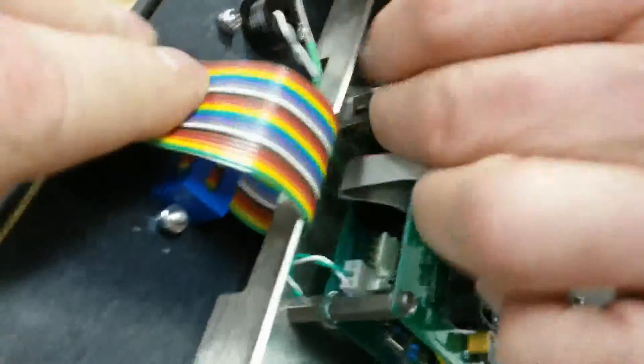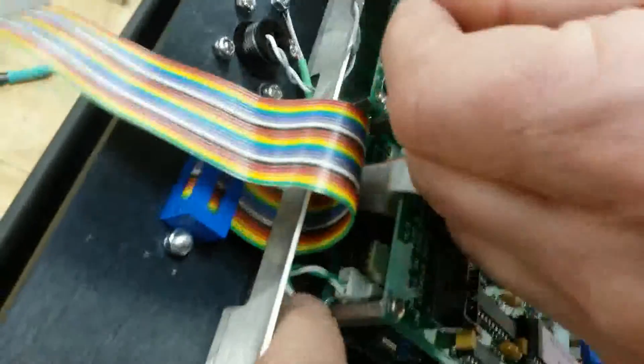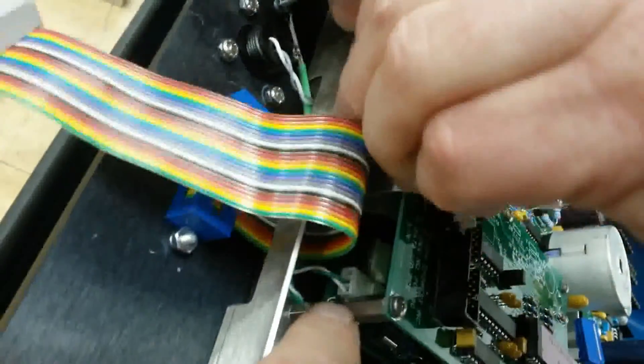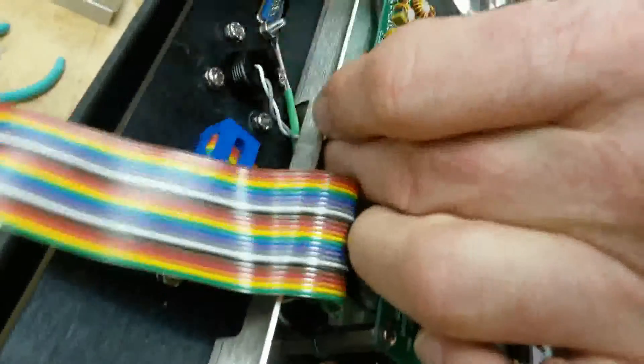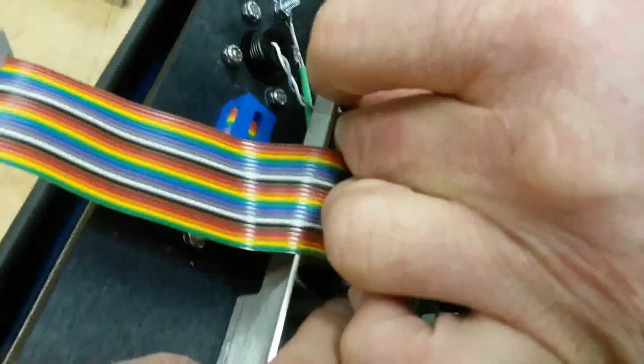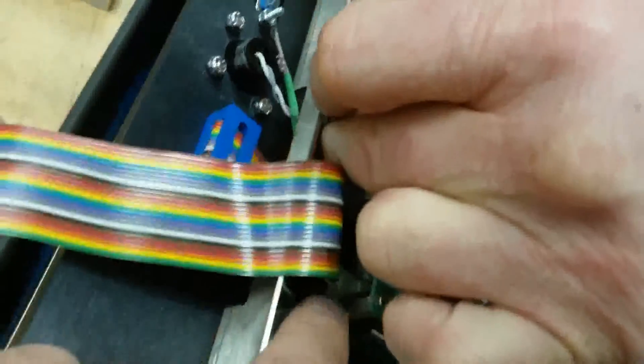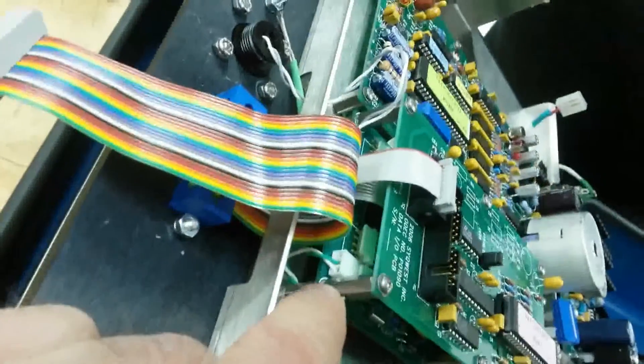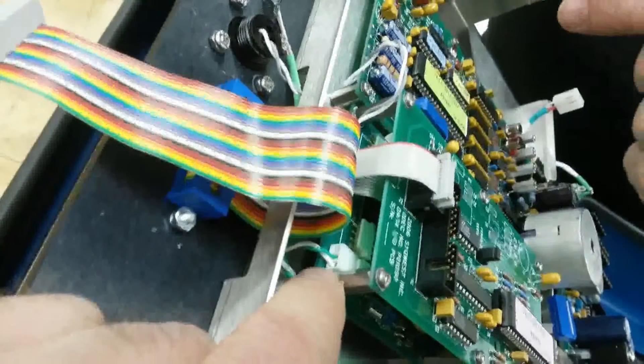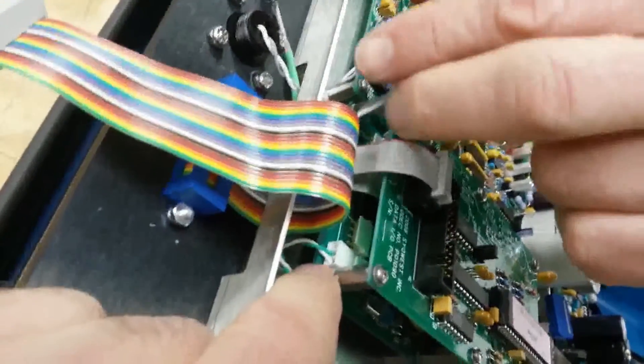This is the keypad cable. This is right here on the CPU, the connector that's closest to the chart paper. That's where the first connector is where the keypad lighting goes.